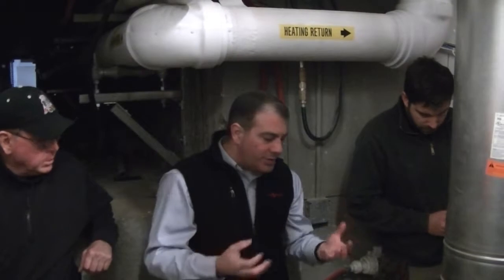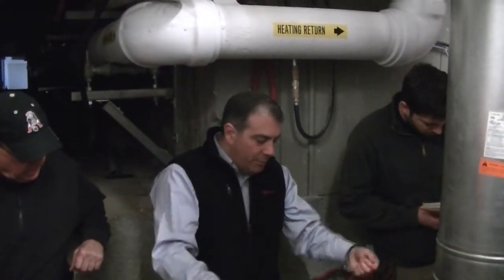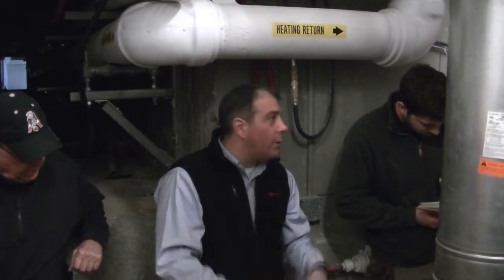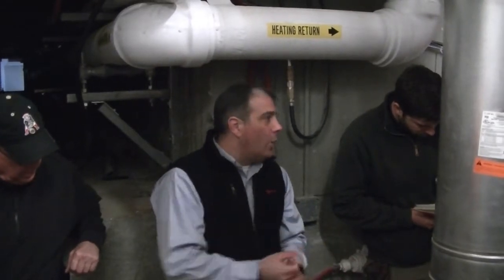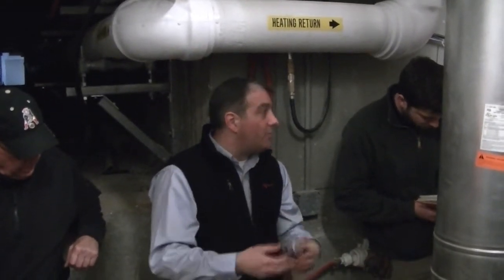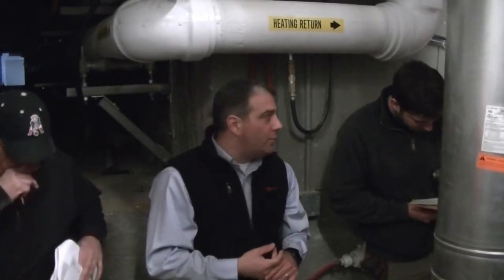So as part of your preventative maintenance service every year, you want to make sure that somebody is monitoring the lime pellets. You can take them out of there, put them in a big spaghetti colander, hose the sludge off, and put the lime pellets back in. Over time, you'll see those lime pellets start to dissolve, and then you fill them back up. That'll usually take a few years anyway.